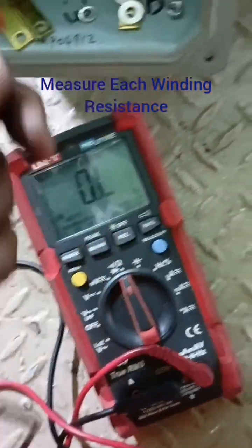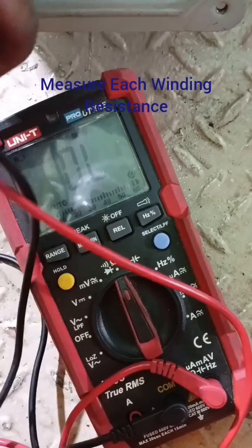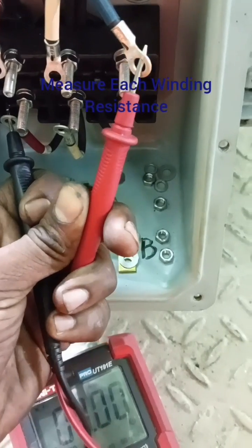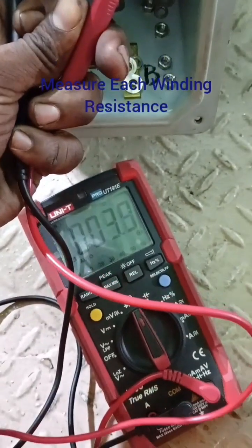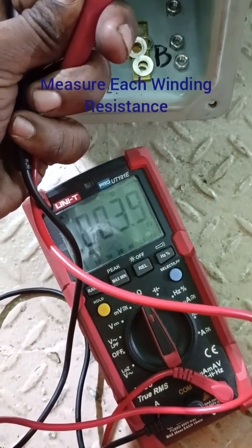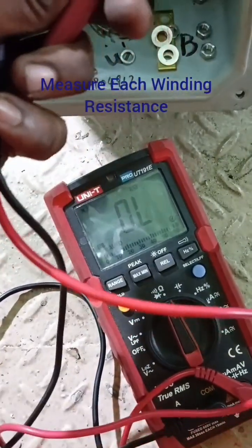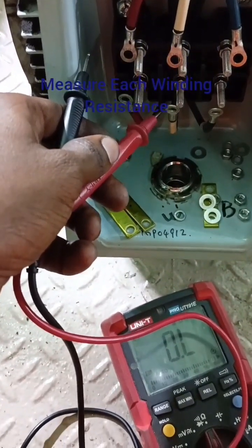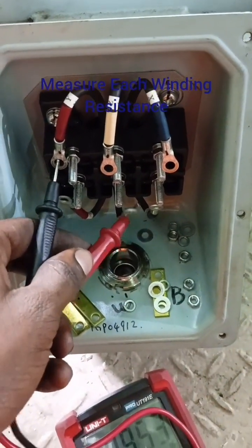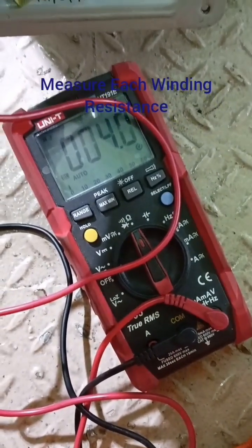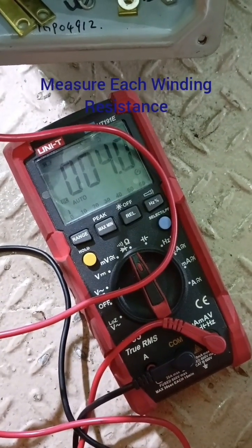So I put the multimeter in resistance mode. Now I am measuring the resistance between U1 and U2. I am getting around 4 ohms. So I will measure the other two windings also. I am getting the same resistance, U1 and U2, 4 ohms, and W1 and W2 I am going to get 4 ohms.